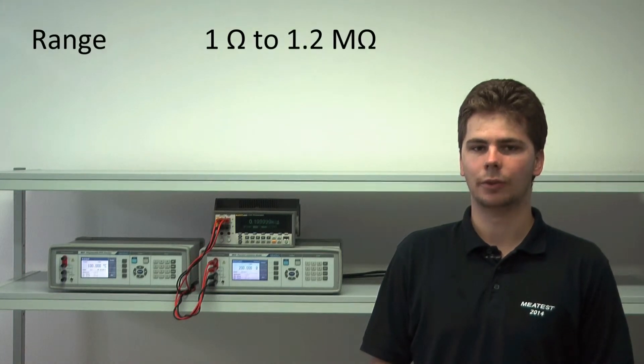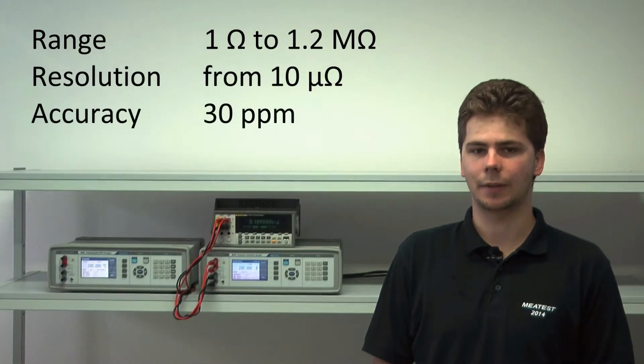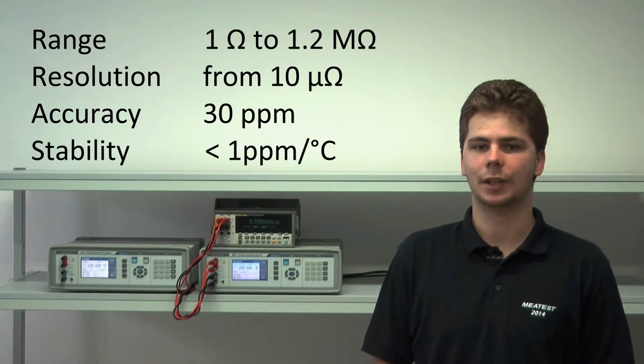The M632 programmable decade operates in continuous range from 1 ohm to 1200 kilo ohms with low range resolution as high as 10 micro ohms, accuracy from 30 ppm and temperature stability of less than 1 ppm per degree C.